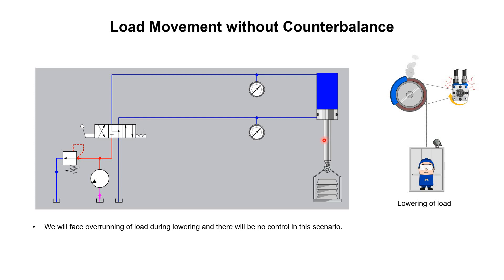But when we are lowering this load, we have the same overrunning problem. When fluid enters the above side of the cylinder, due to gravity — assume this weight creates an extra 100 psi of pressure — we will again face overrunning. The load will move in an uncontrolled manner. For example, if the hydraulic circuit is supplying 50 psi but the load adds 100 psi extra, we effectively have 150 psi on the above side, and the load will move with a higher, uncontrolled speed.